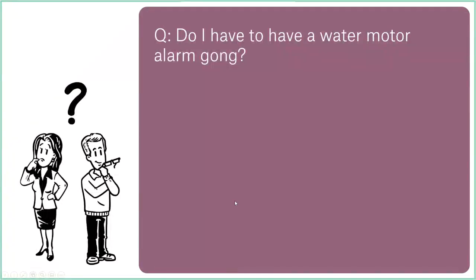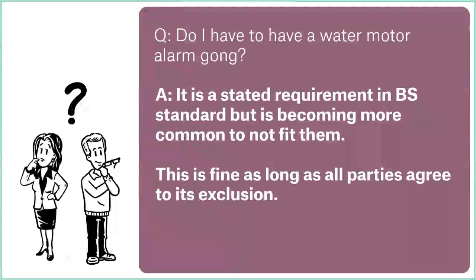Next question: do I have to have a water motor alarm gong? Well, yeah, sort of. In the BS standard, I'm going to read here from 16.1.1 of 12845. It says each control valve set shall be provided with a water motor alarm in accordance with EN 12259 part 4. Okay, so it is there in black and white that you will have a water motor alarm gong. So that's why they're fitted.